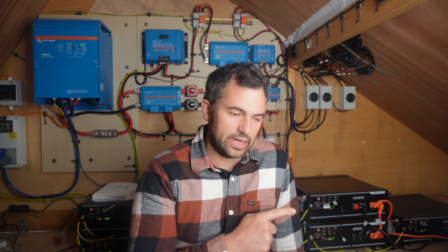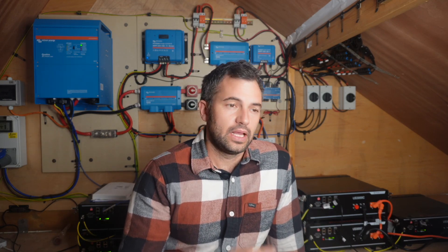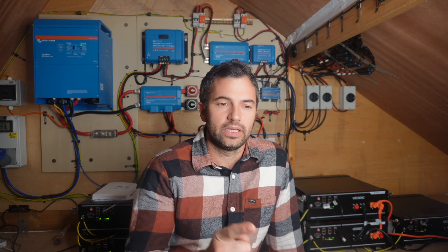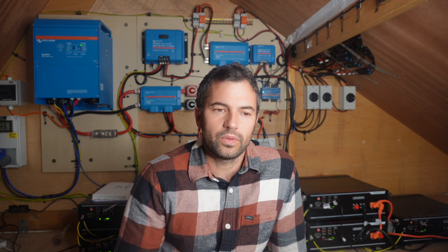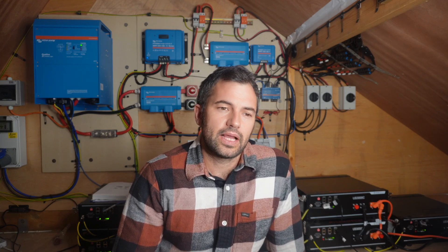We've moved battery 6, which was causing all the problems and setting the alarm off, to where battery 7 was — right on the end. So this communication issue they're suggesting shouldn't carry on; it should be able to not have to relay back, as they suggest. We'll test it tomorrow — run it down below 70% and see if that's right.